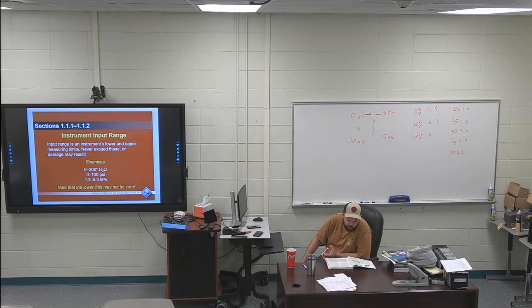They're going to have a couple questions on figuring out what that is. On page 3, the second and third paragraphs go through how to figure out what the span and the range are. I'm going to read through these two paragraphs so you have an idea, but you're going to have a couple questions where you have to figure out what the range and what the span is. And it is confusing. People do get confused by these, so when you're going through these questions, make sure you have an accurate separation of definition between range and span. So when the minimum zero value for range is a number other than 0, an additional step is required.